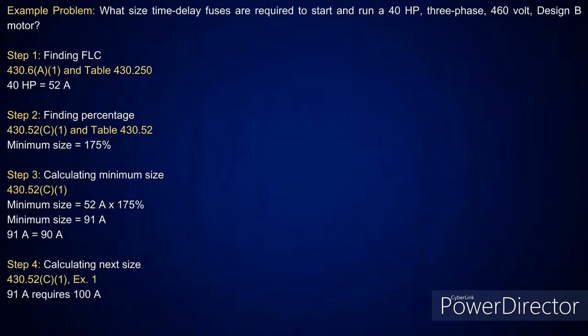All I'm doing different here is I'm going to do a time delay fuse. I already know I was at 52 amps. So all I'm looking at now is what percentage do I use for a time delay fuse? Well, if I look at table 430.52, come down to squirrel cage motor, it's going to tell you for time delay, 175%. Same calculation. 52 amps, only instead of 300, I'm doing it at 175%, gives me 91 amps. I can't exceed the calculated value, so I drop down to 90 amps. Then I look at exception one for the next size. The next size above that would be 100 amp.